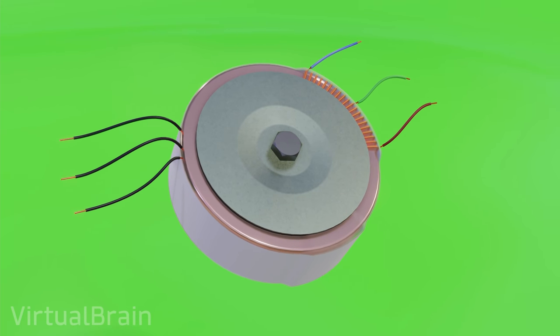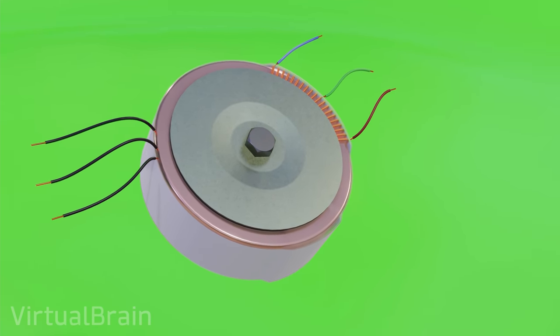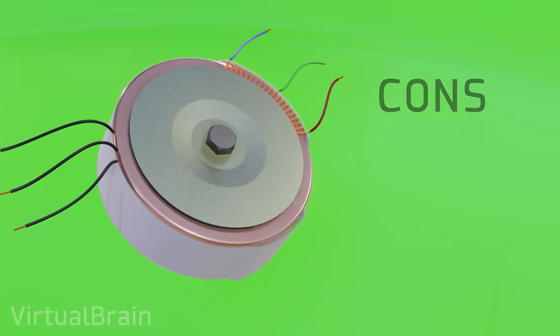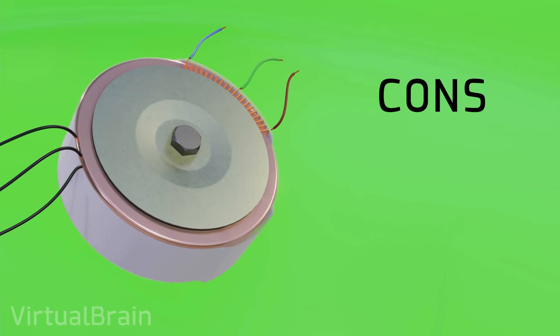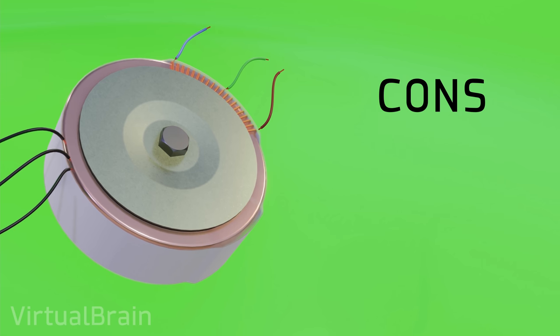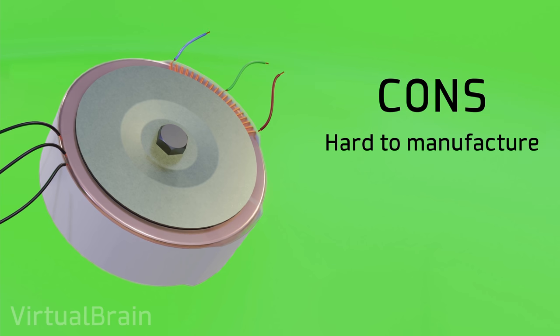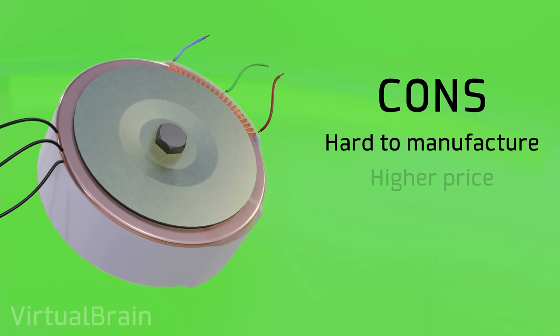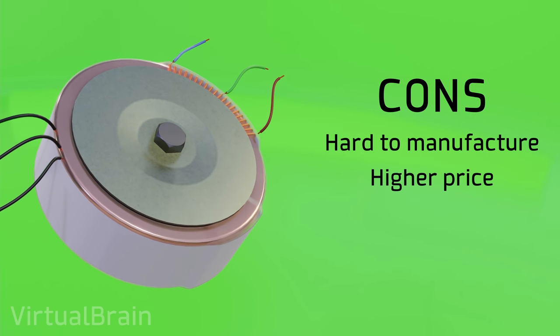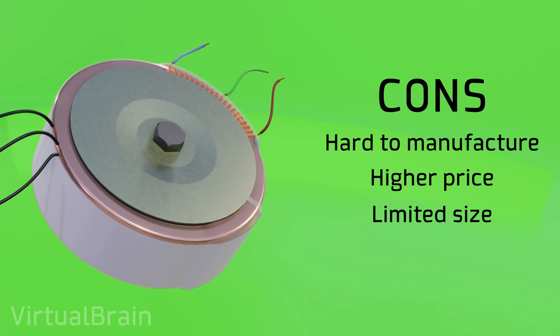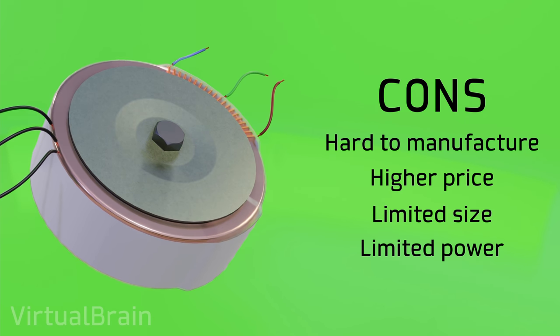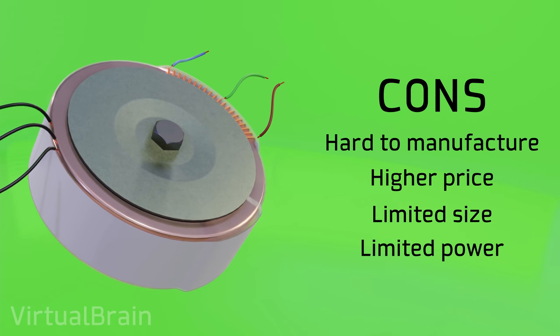Now that we understand all the benefits of toroidal transformers, the question is why don't we use them everywhere? Unfortunately not everything is perfect, because, due to their shape, these are usually more difficult to build than other types of transformers, which implies that they usually have a higher cost and that generally are not usually found in very large sizes, limiting the maximum powers to which they can operate to only a few kilovolt ampere.